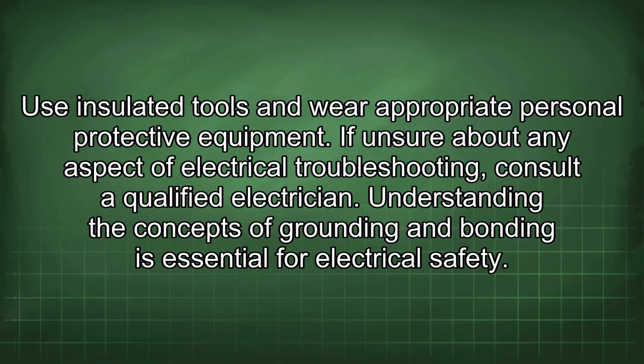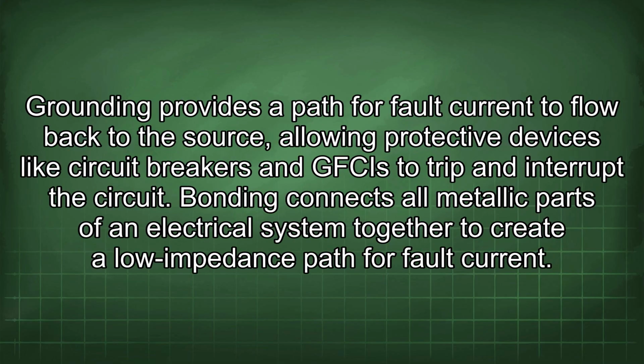Understanding the concepts of grounding and bonding is essential for electrical safety. Grounding provides a path for fault current to flow back to the source, allowing protective devices like circuit breakers and GFCIs to trip and interrupt the circuit. Bonding connects all metallic parts of an electrical system together to create a low impedance path for fault current.